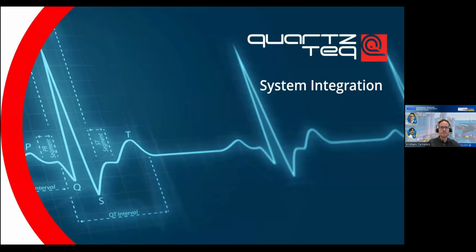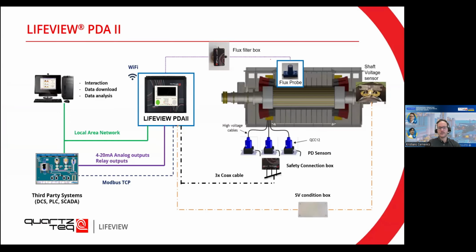And then, yeah, for the last part, I want to tell you about the system integration. As you now know, all three possible measurements, the shaft voltage measurements, the flux probe, and the PD measurements, can all be combined on one machine through some safety connection boxes. They can be connected to your measuring device. In this case, it's the LifeView PDA, which is your measuring device.